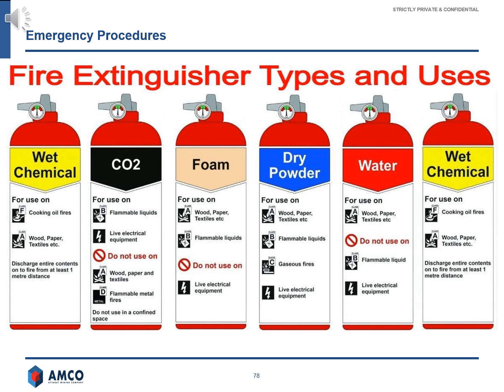Water-based extinguishers should never be used on electrical fires because water conducts electricity, which can lead to electric shock and potentially spread the fire. Foam extinguishers, similar to water-based extinguishers, can conduct electricity and should not be used on electrical fires.